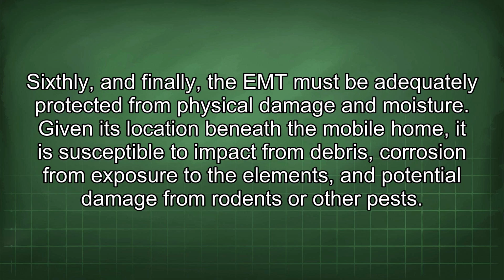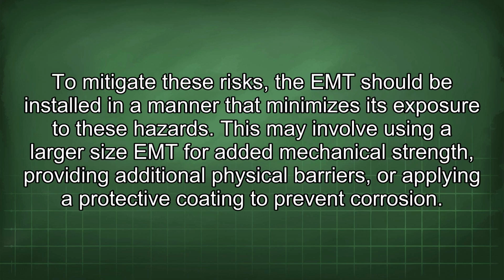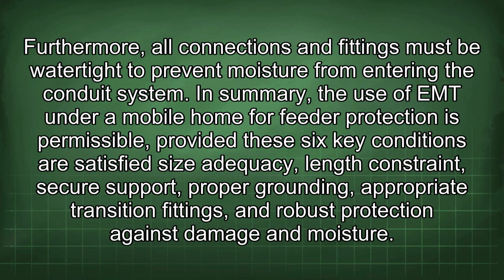Sixthly, and finally, the EMT must be adequately protected from physical damage and moisture. Given its location beneath the mobile home, it is susceptible to impact from debris, corrosion from exposure to the elements, and potential damage from rodents or other pests. To mitigate these risks, the EMT should be installed in a manner that minimizes its exposure to these hazards. This may involve using a larger size EMT for added mechanical strength, providing additional physical barriers, or applying a protective coating to prevent corrosion. Furthermore, all connections and fittings must be watertight to prevent moisture from entering the conduit system.